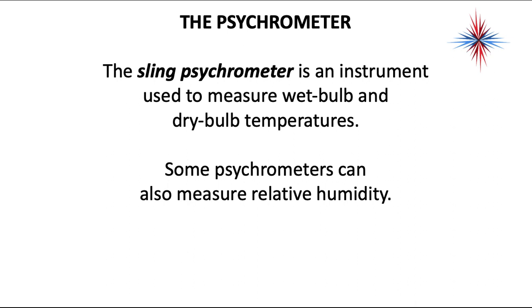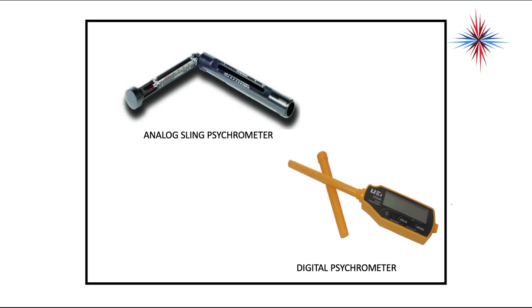The sling psychrometer is an instrument used to measure wet bulb and dry bulb temperatures. Some psychrometers can also measure relative humidity. Back in the day, before digital psychrometers, you used a sling psychrometer with two thermometers. One thermometer had a wick you'd put distilled water on, and then you'd twirl the instrument in the air to cause airflow across the thermometers, giving two different readings. Now we have digital psychrometers — you just put the probe into the airstream and it takes both wet and dry bulb readings.